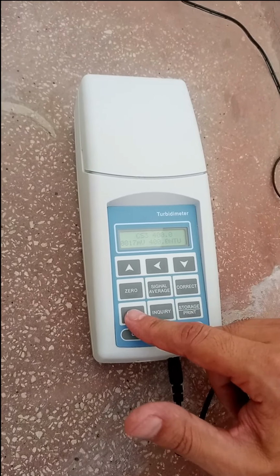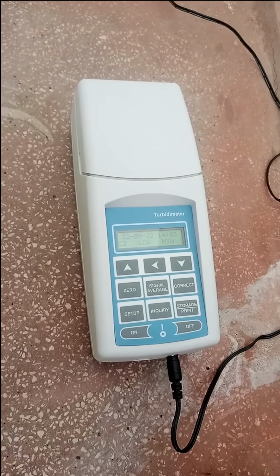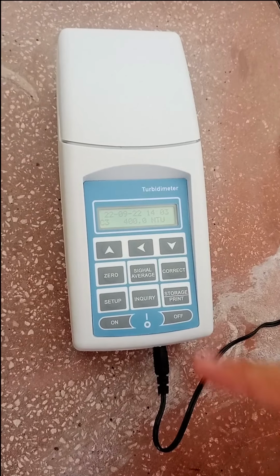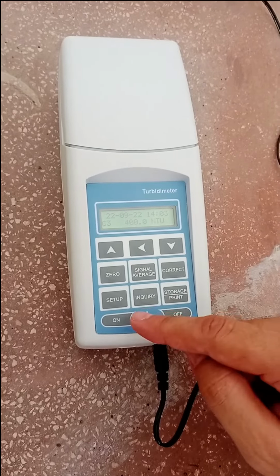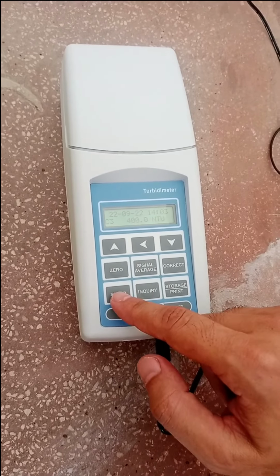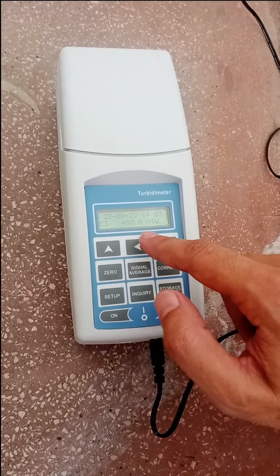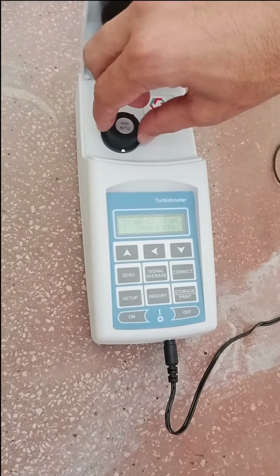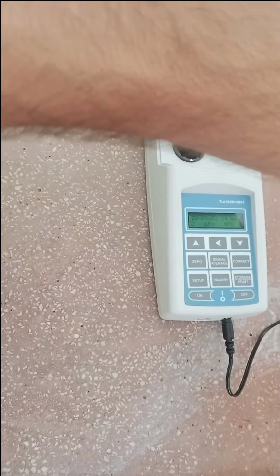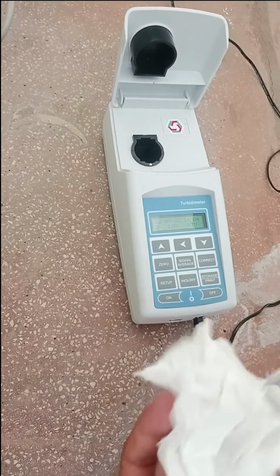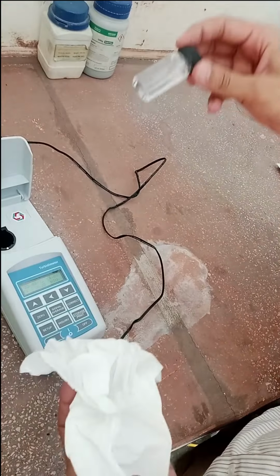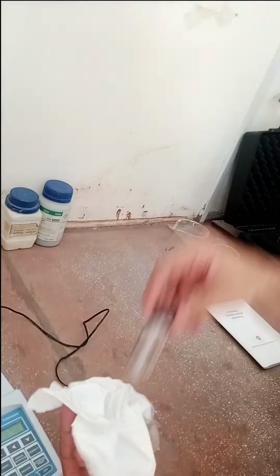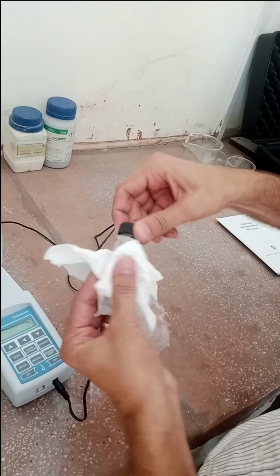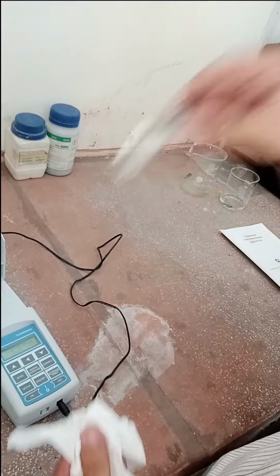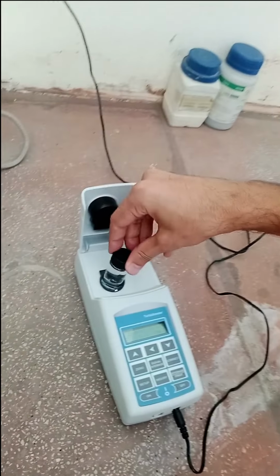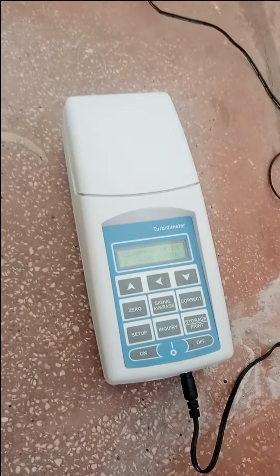Now press the setup button to come out of the calibration mode. When we bring the machine back to the normal measuring mode from the calibration mode, it gives the value of 400, which means our machine has been calibrated as per the given sample. Now let's measure the tap water. We have taken the tap water, the same amount, in the bottle, cleaned it, and with a bit of shaking, place it in the chamber.